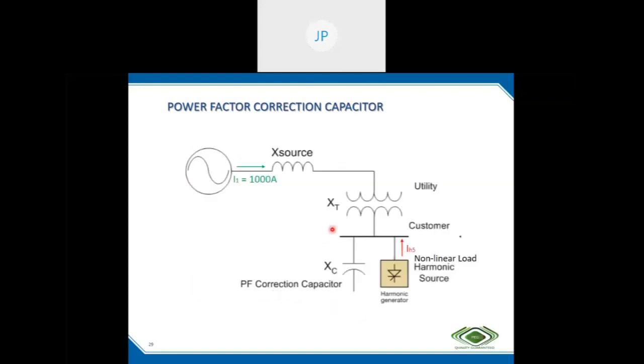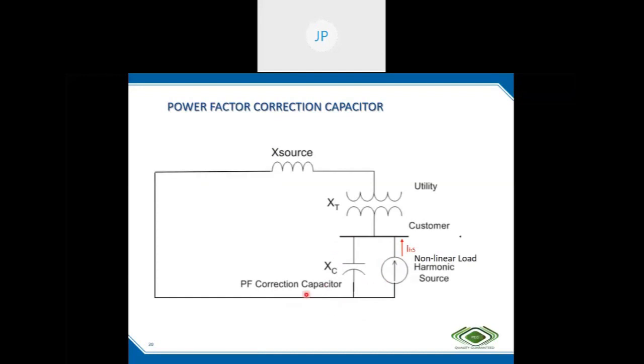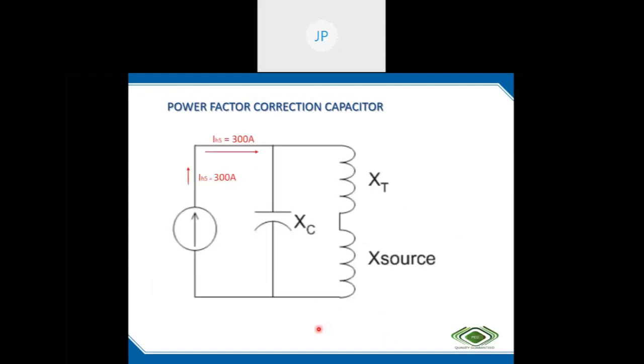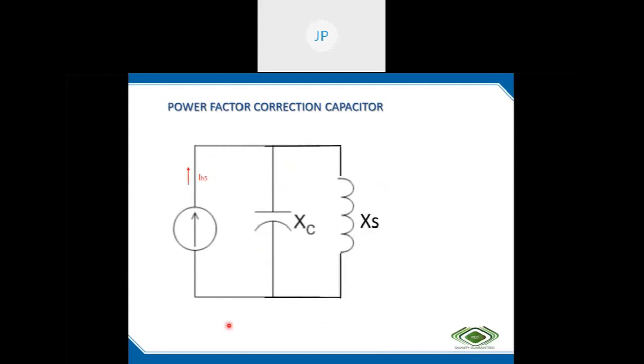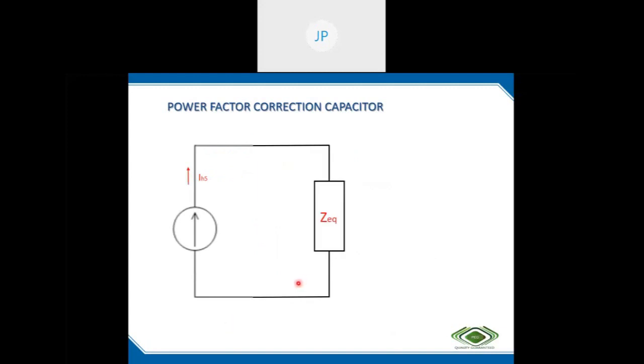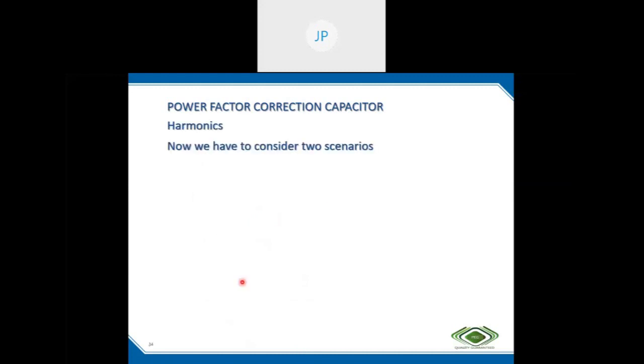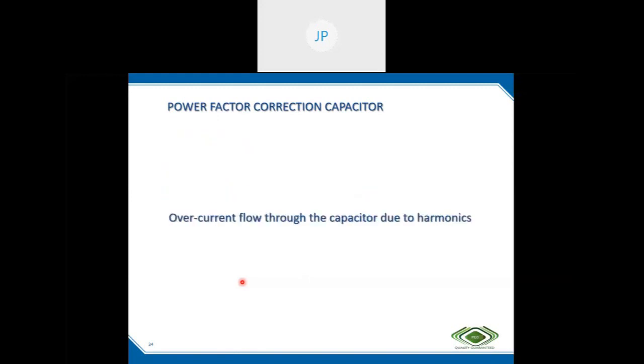Next, we are considering that a capacitor is connected. This also we have to simplify. An additional element is here. We are considering only the current source. This is the simplified diagram. If we want to analyze the current flow in each branch, we can consider this one, otherwise we can simplify it further. This will be useful to calculate the voltage across these elements. So now we have to consider two scenarios. First is the current flow in the capacitor bank due to harmonics. The other is harmonic amplification due to resonance. So we can consider these overflow scenarios now.